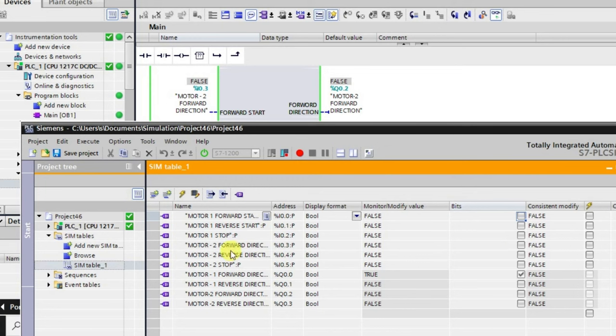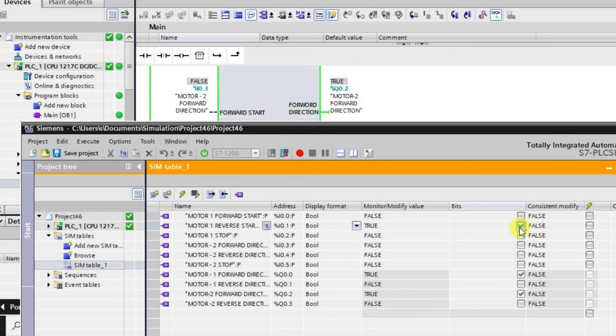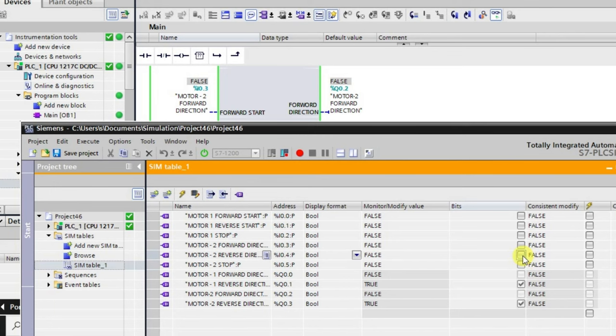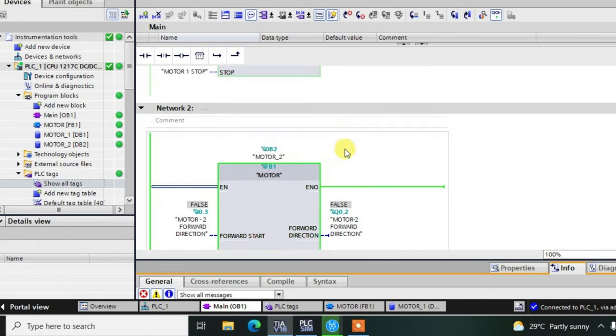I'll start motor number one in the forward direction by clicking and releasing — you can observe the forward direction motor is now in the ON state. We can also turn on motor number two in the forward direction. Both motors' forward direction is ON. Now if we try to reverse while forward is running, it is not possible because we have used interlocking. We need to stop it first, then reverse — and now motor two is running in the reverse direction.